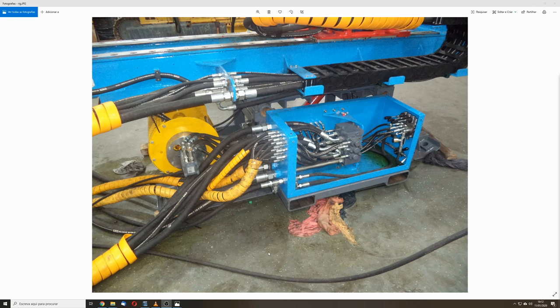Because in certain cases, the standby pressure can be significantly higher than the actual delta P. And for such systems, adjusting the delta P from the standby alone usually results in an incorrect setting, which is exactly the case of the hydraulic system that we are about to see here.